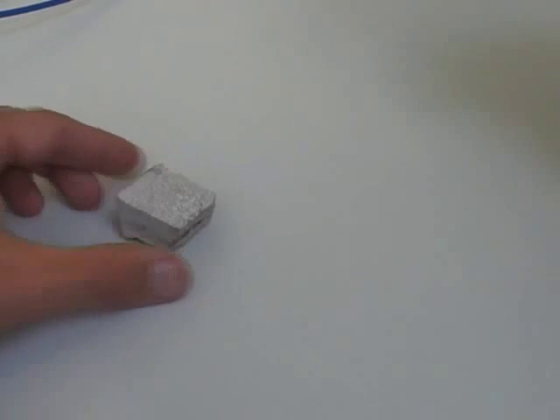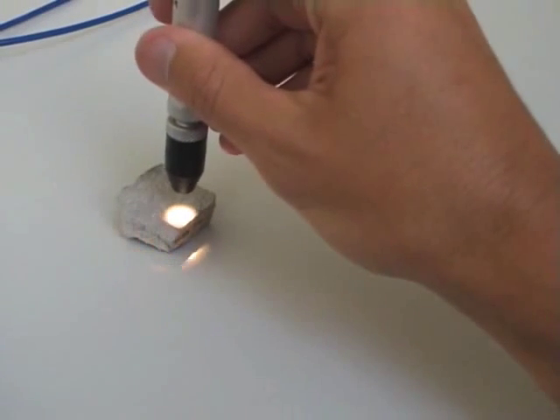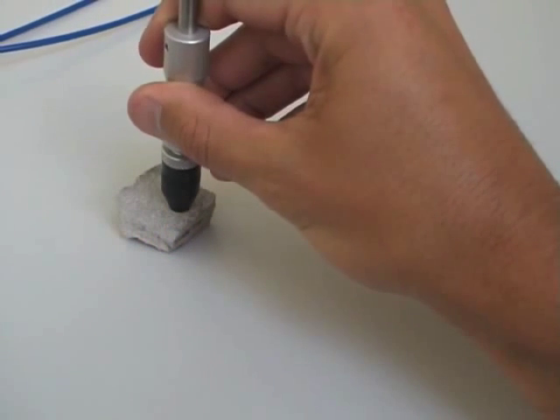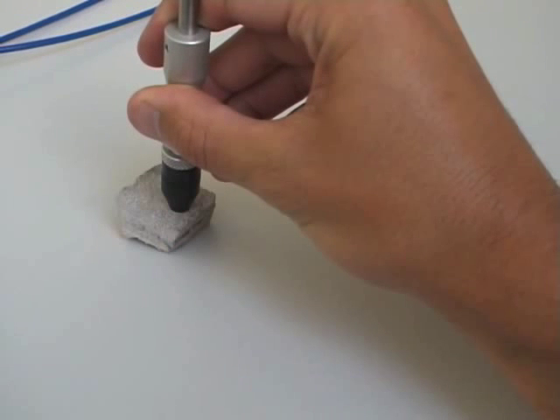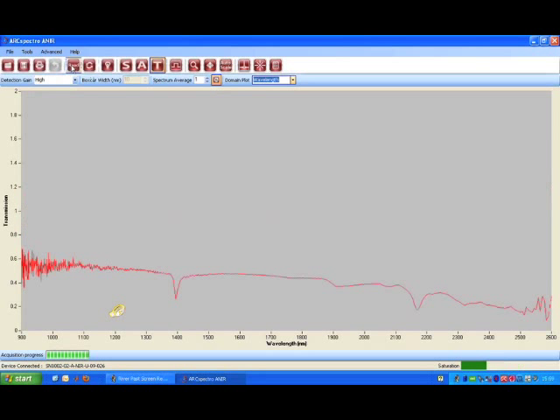To measure your sample, simply press the tip of the fiber probe onto its surface, as you did with the white reference standard. Press the read button, and then autoscale.